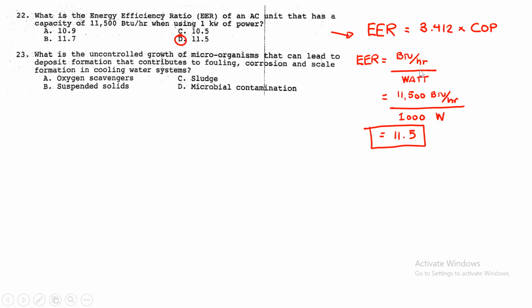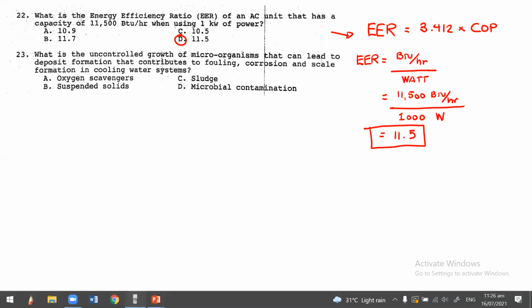Parang i-convert mo lang into the same unit. So, BTU per hour yung isa, watt yung isa. So, diyan nanggaling yung 3.412. Kung i-convert mo itong 11,500 BTU per hour, so 2,545 BTU per hour per HP. Then i-convert mo into watts, so times 1 over 746 watts per HP. So ayan, diyan nakuha yung 3.412. So parang conversion nga lang yan, BTU per hour per watt.